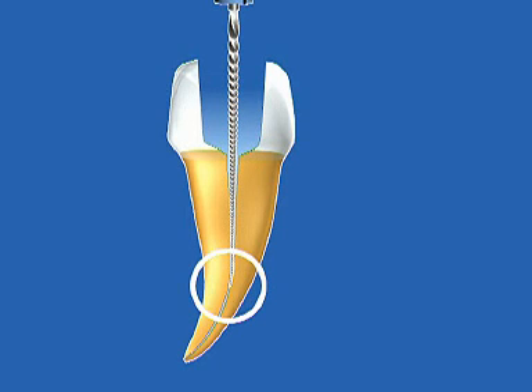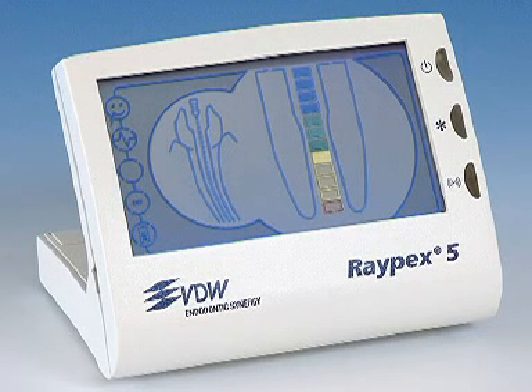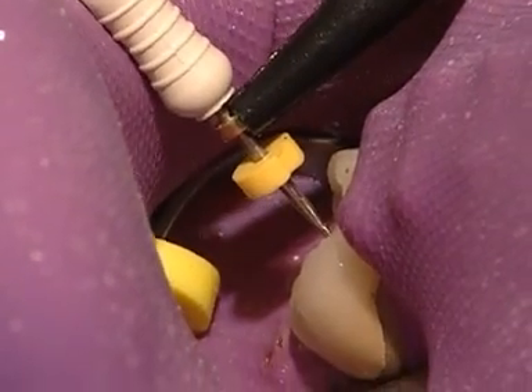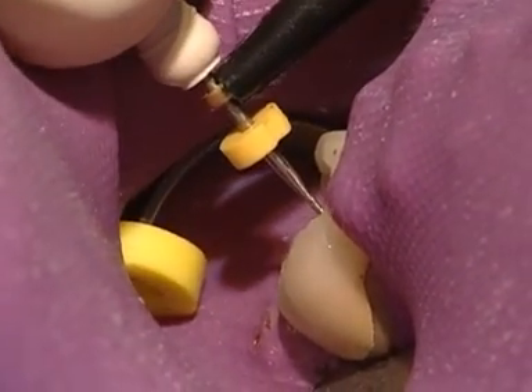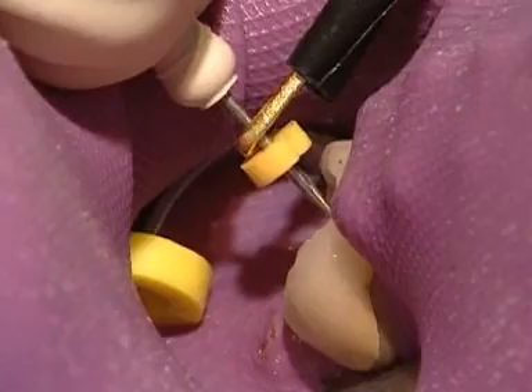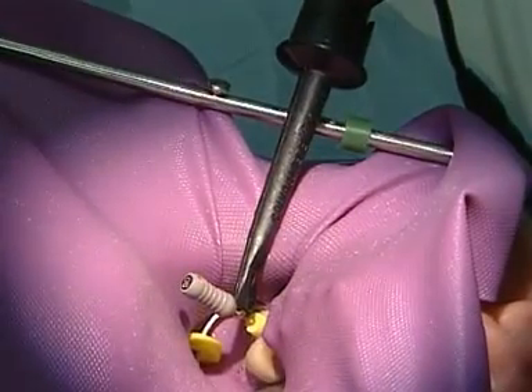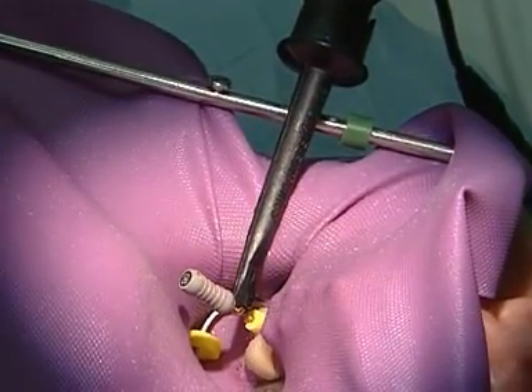When 2/3 of the estimated working length has been reached, exact canal length should be determined. For this, an electronic instrument like the Raypex 5 is almost indispensable. Raypex is more accurate than an X-ray, and because of this, it is not necessary to take an X-ray at this point.